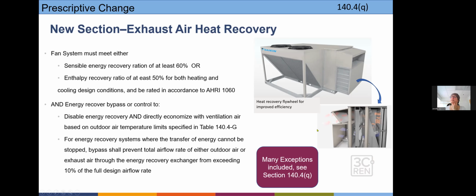In this case, we're in a cooling mode. As the air comes in through the unit, it's tempered by this flywheel, and we've got exhaust air coming out through the unit so that the flywheel helps temper the incoming air by using the energy from the outgoing air, or in cooling mode, the lack of energy in the outgoing air. So that's a visual of what these systems look like.